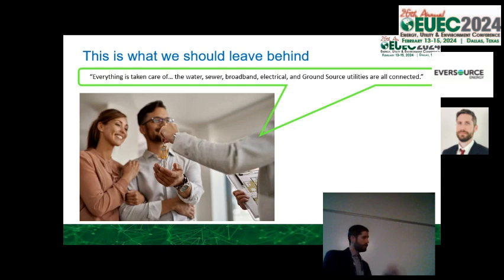Because you're pulling the temperature from the ground, which is a constant temperature, right? Even if the air in Buffalo is at negative 10, the ground is still that same constant temperature of somewhere in the 50s. 58, yeah. And for context, on our designed system here, on the design day, the coldest day in Massachusetts that we're expecting, the loop temperature will never get below 39 degrees in the worst case. So we should range between about 40 and a little over 70 in the middle of the summer and keep that nice tight band year round.